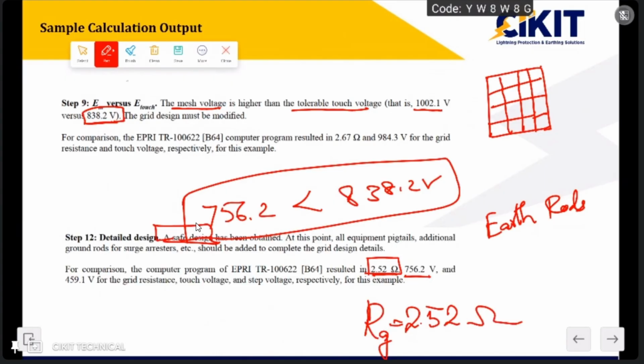So from this conclusion, we can observe that even though the earth resistance value is not less than 1 ohm, the design can be considered safe if the step and touch voltages are within the tolerable limit. I have just provided the output of this calculation alone. If I wanted to explain the complete calculation, it would take another half an hour. I have shown only this output to highlight the point that for safe designing, the earth resistance value is not the designing parameter, whereas the actual designing parameters are the step and touch voltages.